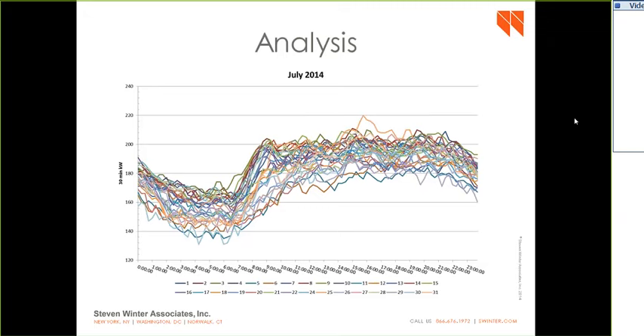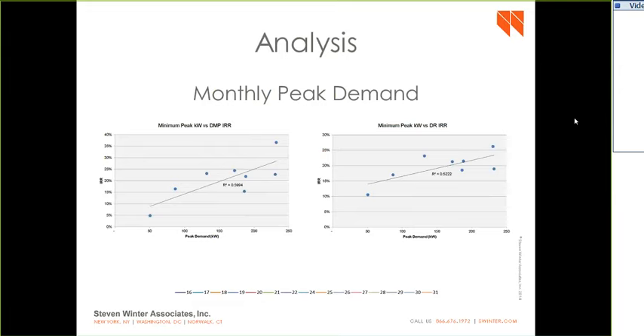And specifically, we also found that of the peak loads, if you take all 12 out of that year and take the smallest peak, typically in the winter, January, February, that is the one that is most correlated with financial performance. So the higher your peak load is when it's the smallest, if that makes sense, the more you're going to be able to drive savings.